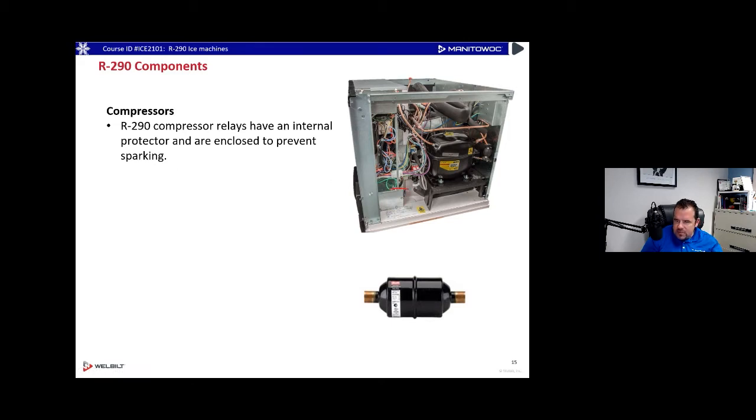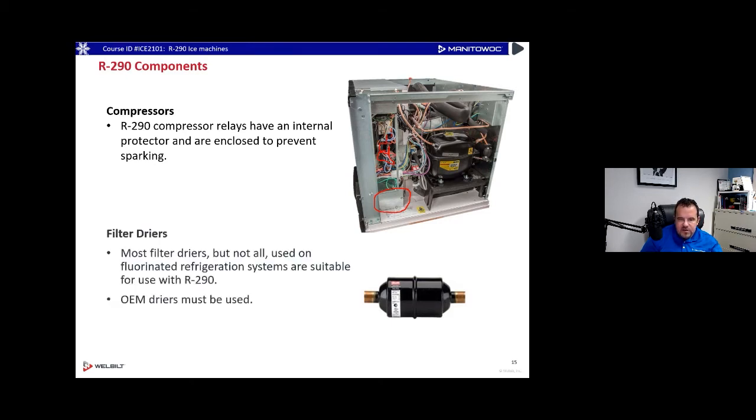R290 compressor relays have an internal protector and are enclosed to prevent sparking. On our Indigo NXT — which is 50Hz only, not sold in the US currently — there's a small extra enclosure box for the compressor contactor to prevent sparks. Normally you'd see the contactor on the regular control board area, but on R290 it's placed in this enclosed little box. Also, most filter dryers — but not all — used on regular refrigeration systems are suitable for R290.